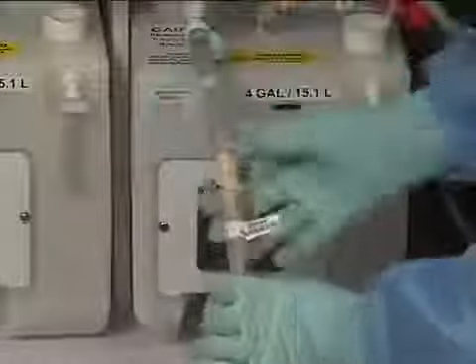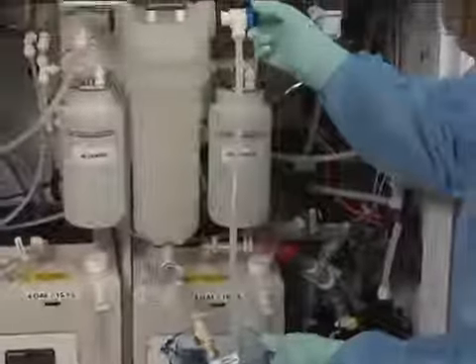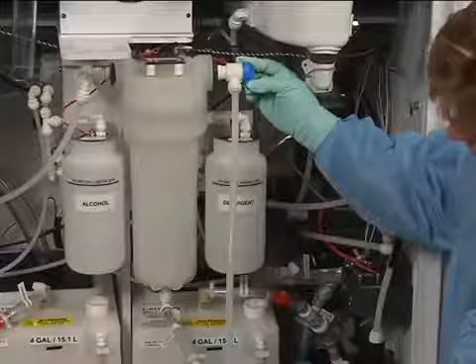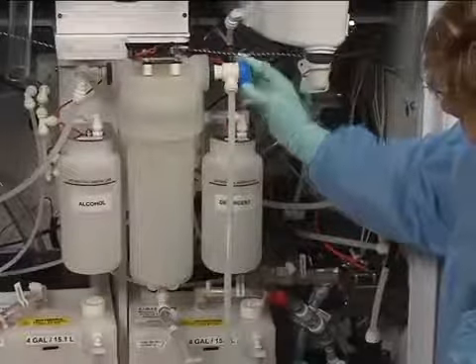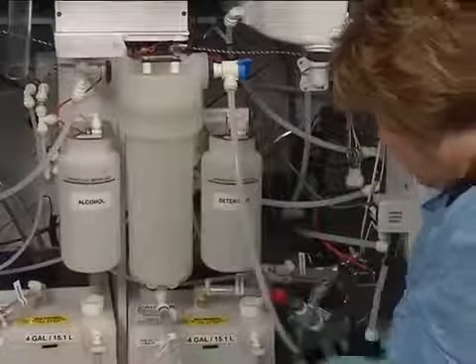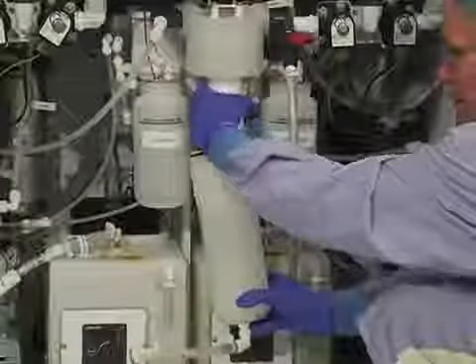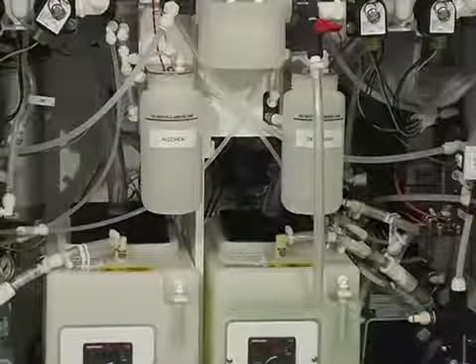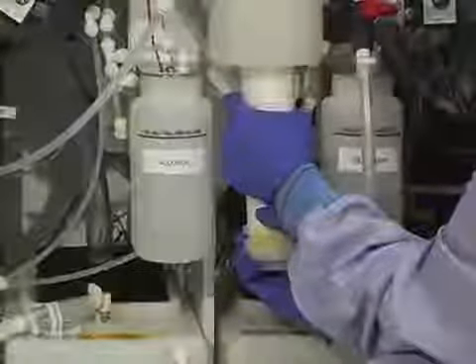Attach the accessory hose. With the accessory hose pointing toward a large container like a bucket, slowly open the air bleed valve near the top of the filter housing and drain water from the housing. Loosen the internal housing using the filter wrench and remove. Wait for the water to drain from the housing. Rotate the filter to the left to unlock it, remove, and discard the filter. The housing can be cleaned by washing and brushing with a neutral pH, low-foaming medical-grade detergent, rinsed, then dried with a lint-free cloth. Install a new filter by placing it into the filter cap and pushing the filter upwards into the filter housing cap. Turn the filter to the right to lock into place.